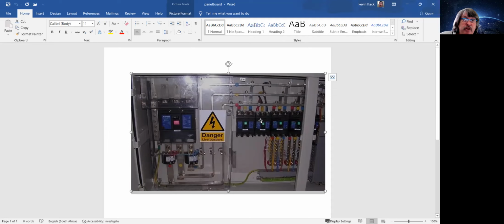an alternative problem. So when we look at this sort of product that we've got connected in here, this interface between the main upstream breaker and then smaller downstream breakers becomes quite critical, especially when the large breaker is much larger than the breakers downstream. I'll show you on the load side where there's definitely a problem on this one. So let's have a look here. We've got a 600 amp breaker. It provides all the protection all the way up to this level down here, up to this zone down here.